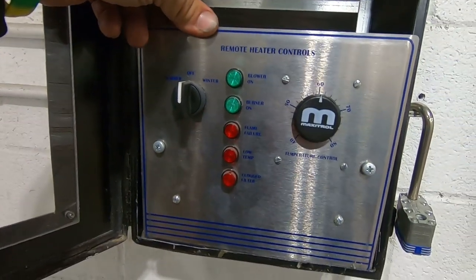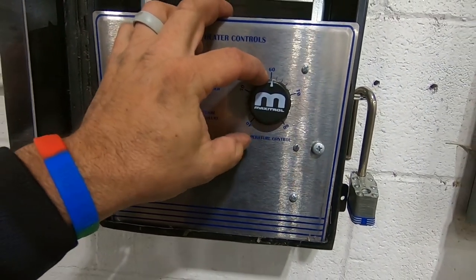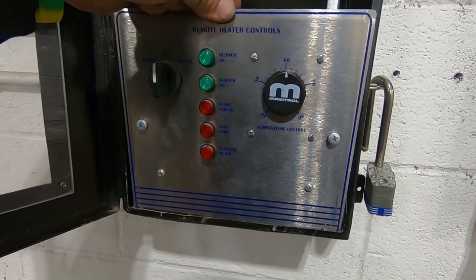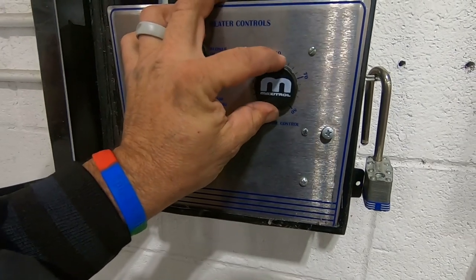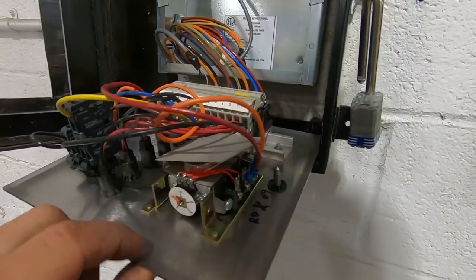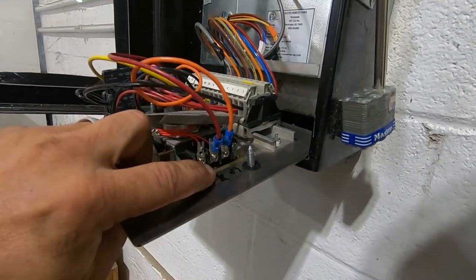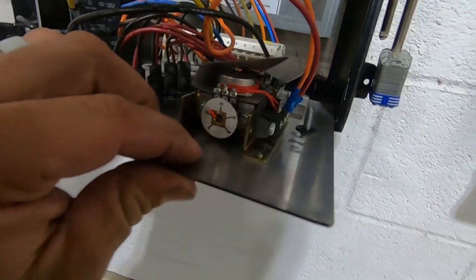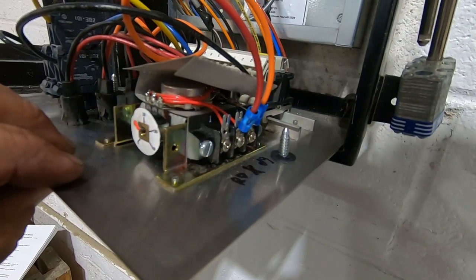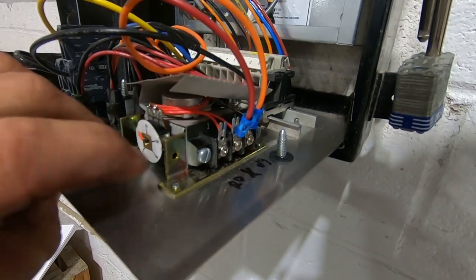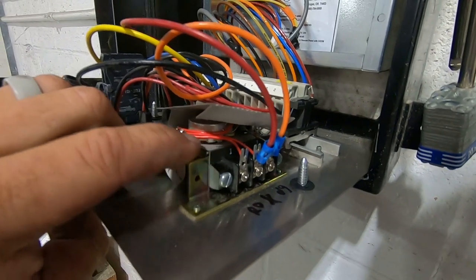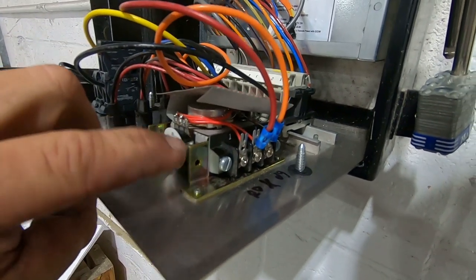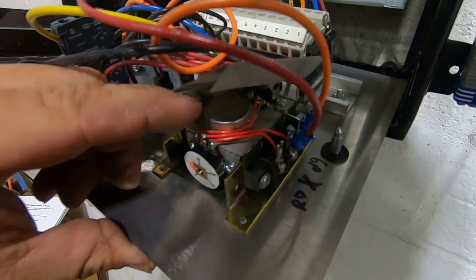Okay, as we're looking at the temperature control on the inside, this control has a temperature relation chart and it's supposed to be on probes one and three here. You've got a calibration spot right there. Basically, I checked it, had to call the factory, get the chart. It appears that these might have been wired wrong because I couldn't calibrate it. But when I checked my calibration through here, because if you look at how that's wired...